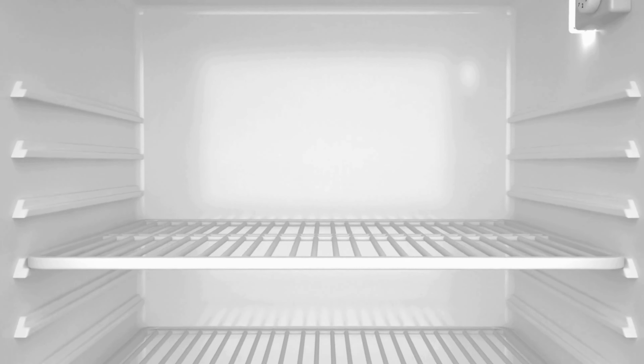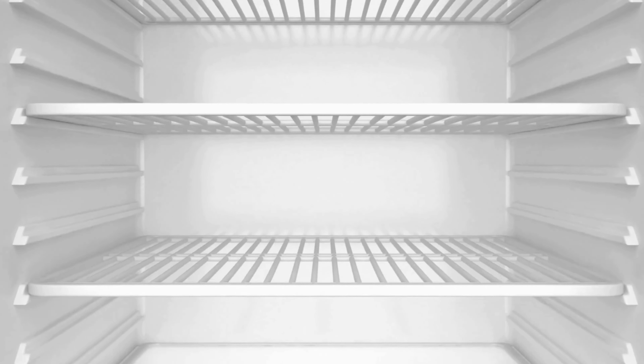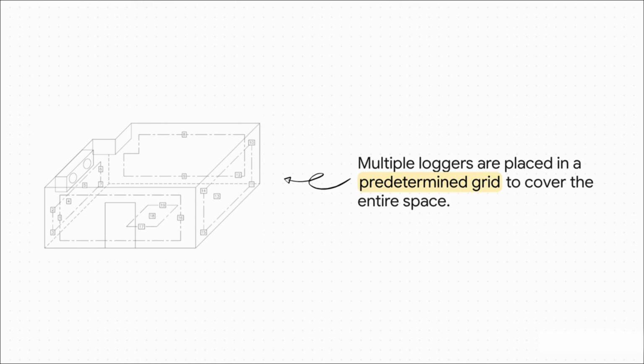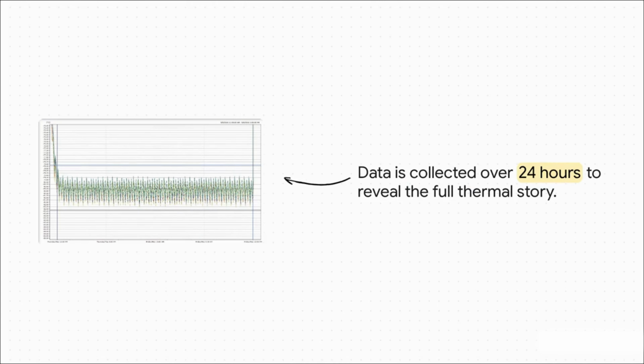And of course, you don't use just one. You place multiple data loggers all throughout the freezer in a really strategic, pre-planned grid. You want to cover every possible spot: high, low, front, back, all the corners, and right in the center to get a complete thermal profile of that entire space. So these loggers just sit there and record data continuously, usually for 24 hours, maybe more. And what you get is a graph that looks like this. Each one of those lines represents a different sensor. The goal, the dream, is to see all those lines stay packed super tightly together, all inside your required temperature range. That visual right there is your documented proof that the whole chamber is stable and uniform.